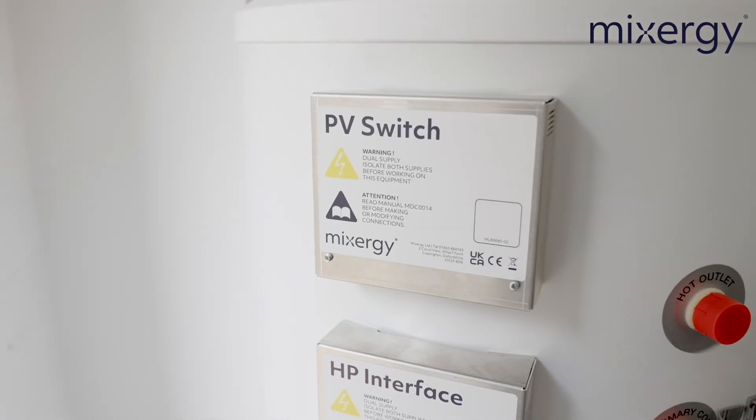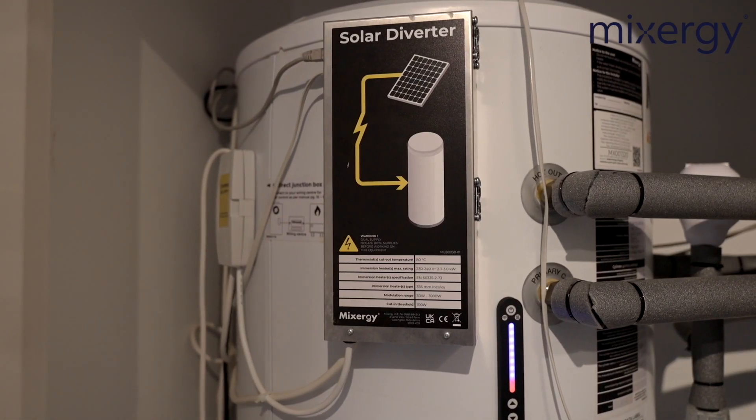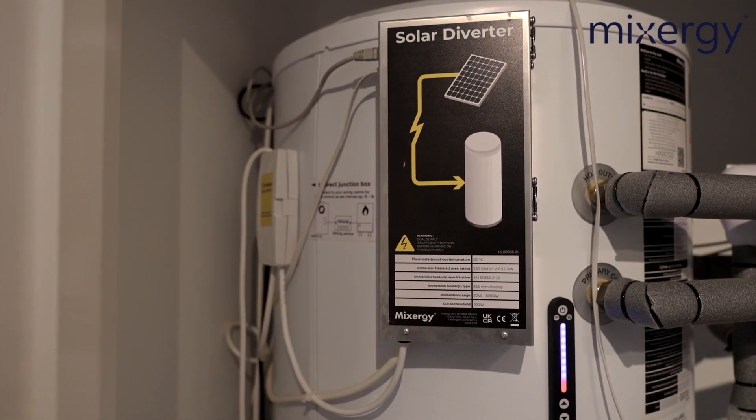Some households will buy a Mixergy tank after they've already had a third-party diverter fitted, such as a MyEnergi Eddi or a Solar iBoost. In this case they will need a Mixergy solar PV switch. Our PV switch converts our immersion heater from a single 3 kilowatt feed to a dual feed — the first is the standard 3 kilowatt feed and the second ranges from 100 watts right up to 3 kilowatts coming from the third-party diverter, meaning we can accept all those variants of voltages into our immersion heater. When installing the Mixergy PV switch: the first consideration is where to mount the PV switch itself — you can mount it on the tank or on the wall near the tank. The second is that you'll need to run a cable from the PV diverter into the PV switch. The third is there's a little bit of wiring to change inside the Mixergy itself, but we'll cover that in a separate video.